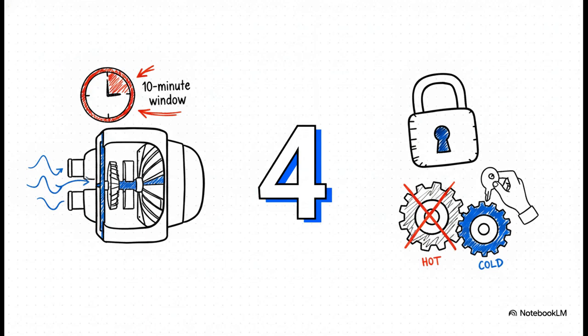Because of that shrinkage, here is the golden rule. If the engine trips, you have a roughly 10-minute window to start a low-speed motoring cycle. This pushes cool air through the engine to stabilize those tight clearances. Now, if you miss that 10-minute window, the control system hits you with a mandatory 4-hour lockout. It absolutely will not let you restart the engine for 4 hours, and guys, this isn't a glitch. It's a critical safety feature designed to stop you from grinding an expanded rotor right into a shrunken casing.